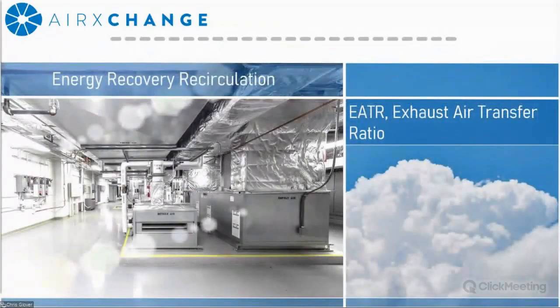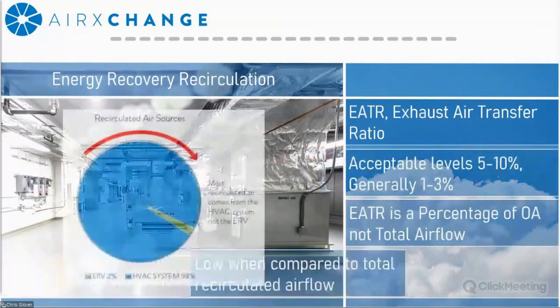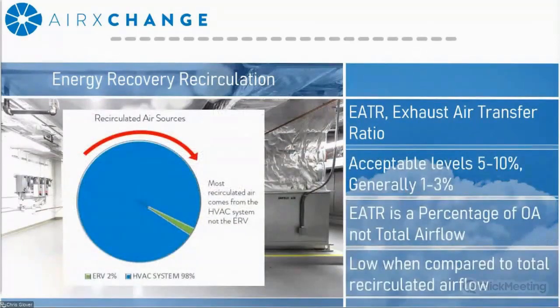So if the energy recovery component is AHRI certified, the recirculation of air is a certified value. In this particular context, it's called EATR, exhaust air transfer ratio. EATR is a value represented as a percentage of the outside airflow, and it gets taken into consideration when designing the fan system. So you're going to have to maintain the net flow to make sure that you're delivering an adequate amount of ventilation air to the space.